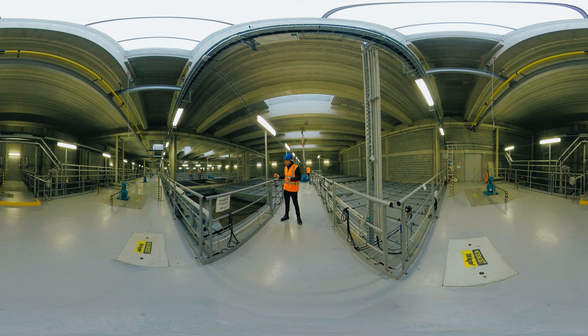What we can see here is the mechanical removal of fat and grease, which there's a lot of in wastewater. Fats have a lower density than water and precipitate up at the surface, so the tanks have skimmers that go round and gather this precipitated grease into a sump. Up to 70% of the solid waste is removed in the mechanical treatment process, both here and by the screens we saw a minute ago. The rest is removed in the biological part — that's where we'll look next.